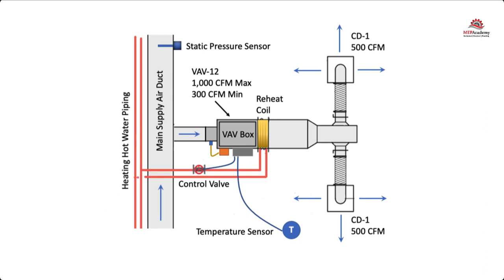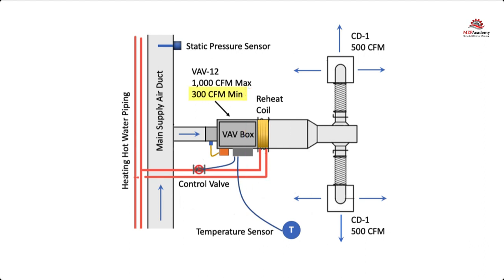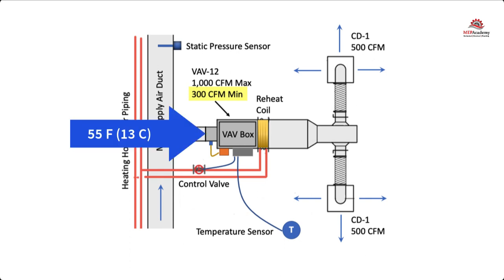During heating mode for exterior zones — and in certain cases interior zones — there will be a reheat coil, a heating hot water coil, or an electric heater attached to the VAV box. When in heating mode, the flow CFM through the VAV box will be at a minimum setpoint to avoid wasted energy, because the air handler is sending 55-degree cold air to all the VAV boxes whether they need heating or cooling. You don't want to send a large volume of cooling air when you want to be in heating mode, so there's a minimum setting for ventilation requirements. That air is coming in at 55 degrees and then you're going to have to heat it up — it's a bit of a waste of energy, but that's at the minimum set volume of air.